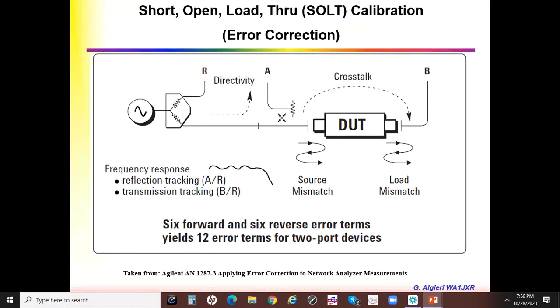And so these are actually metrology grade reference devices that are as close to a perfect short, a perfect RF open, and a perfect 50 ohm load as one can get. And knowing what a perfect short, open, and load should represent from a measurement point of view, the firmware or the software in the vector network analyzer measures all those parameters and calculates the difference between what it measured and what a perfect short or open or load should be. And it stores all those little error constants, those are called error vectors.